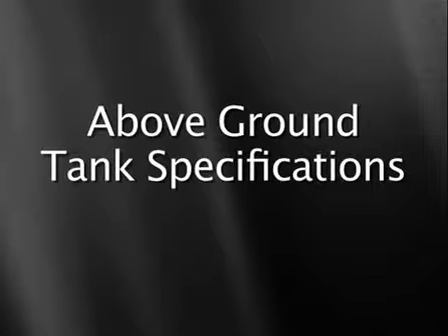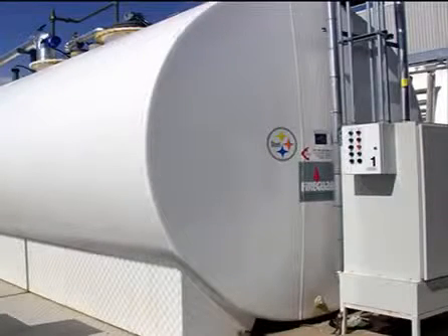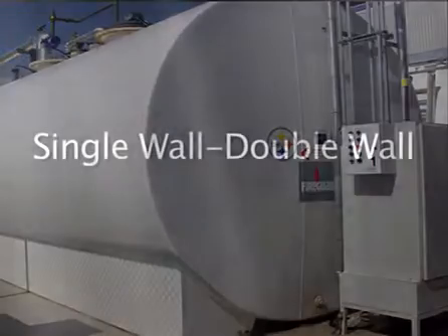Above-ground tank designs have advanced dramatically since the leaking underground tank rules came into effect in 1988. Many people like the basic visual assurance that is missing from an underground system, but like anything, they have their design challenges. Above-ground fuel tanks are made of steel because of its inherent fire resistance compared to fiberglass or plastic tanks. They are more flexible than underground tanks and can therefore conform to a variety of site requirements.